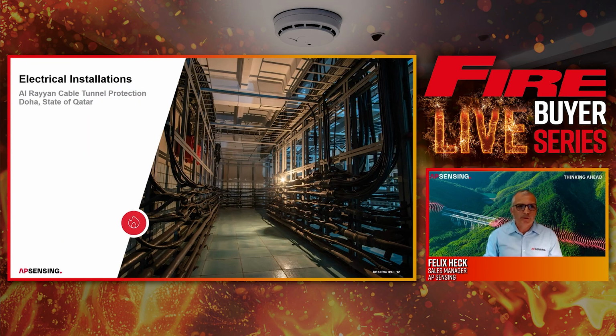Yeah, all around the world, coming to Doha, to Qatar. Here we protect, for example, this electrical installation, a utility tunnel. We can protect either each and every cable length or some connections inside the cable tunnel or the cable tunnel in total. If a fire breaks out, we can send the fire brigade directly to this position. And this is something that is very important if there's smoke distributed and the fire brigade cannot see anything in such a tunnel. This is very dangerous for them.